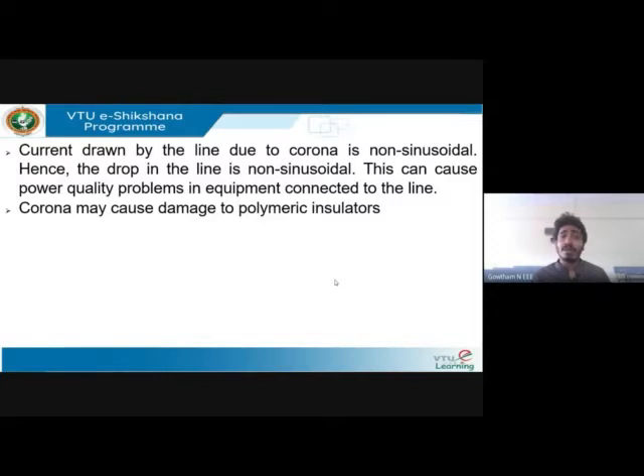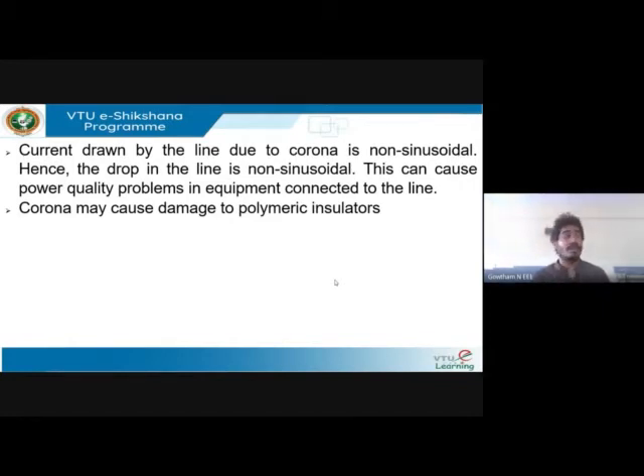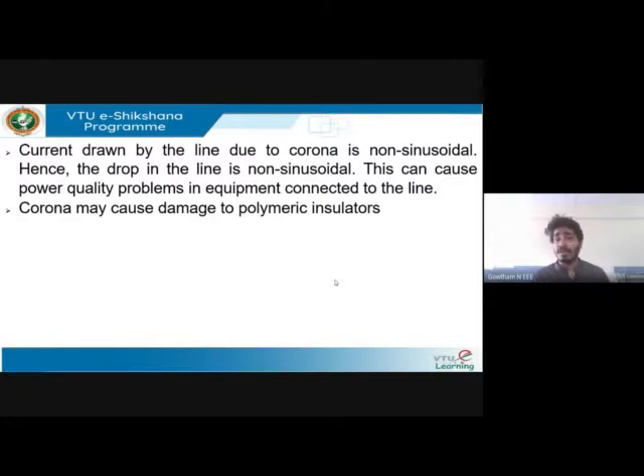Corona will also damage polymeric insulators. Most insulators are made up of polymers or porcelain. When corona discharge flows through the polymeric insulators, they react chemically and their efficacy reduces — the material capability deteriorates. The lifespan of the insulator gets reduced. This is also one of the major effects of corona.